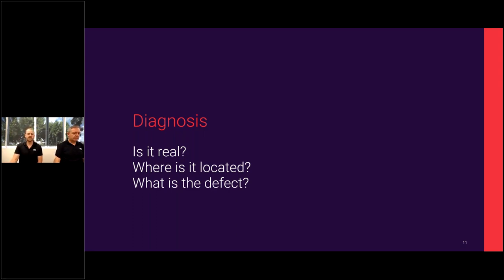Okay, so diagnosis. When we're out in the field and testing for PD activity, the three main questions in our thought process need to be, is it real? Are the signals that I'm detecting from a real PD source, or is it just coming from some sort of background noise that I'm not concerned about at all? So that needs to be diagnosed and answered. Where is it located is the next one.